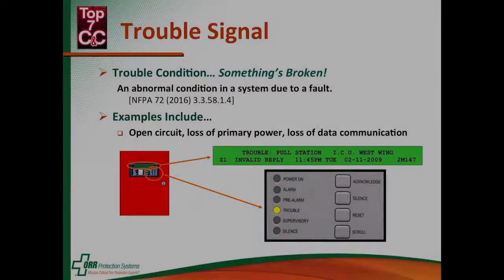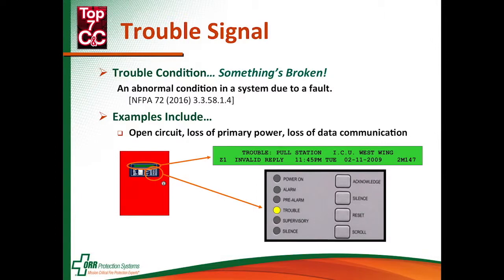Another signal is the trouble signal or trouble condition. It means that something in the fire alarm system is broken. So it could be an open circuit where a wire is broken — we don't have a continuous electrical pathway back to the panel.